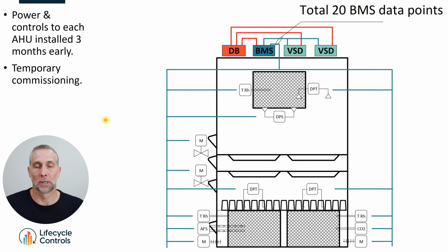So in this situation, you can just put some barriers up here and you can get a temporary power feed onto this BMS panel, like a 24 volts AC power feed, and you can power up the controller, download the program, address the controller, and then start pre-commissioning, driving the valve actuators open and closed, getting the sensors online. Like not everything, some things won't be on here yet, but as much as you can.